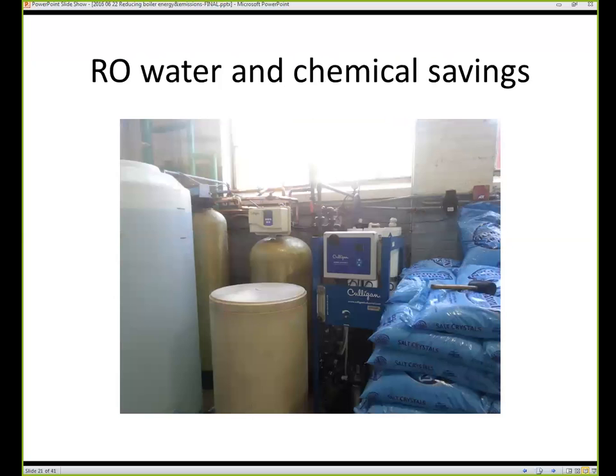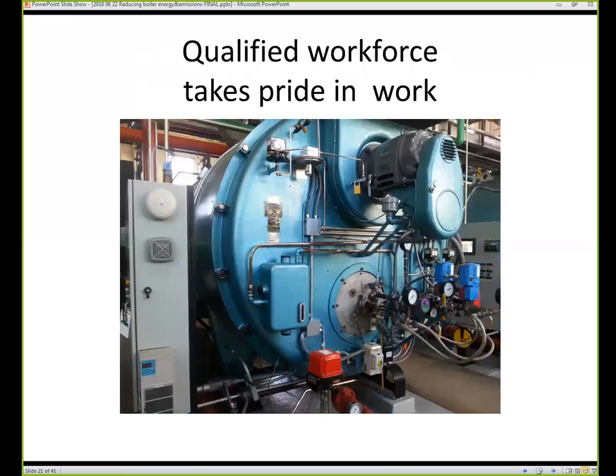Next slide. We installed this RO unit about 8 years ago. We currently have about 92% condensate return, minimal blowdown, and sulfite and polymer costs have gone down. We spend about $150 a month on chemicals, and that's pretty cheap. Our blowdown is minimal, and we use probably 400 gallons of makeup a shift. That's it. And you'll get a payback on an RO unit like this.